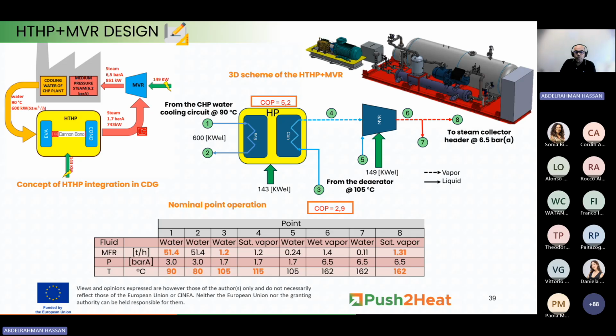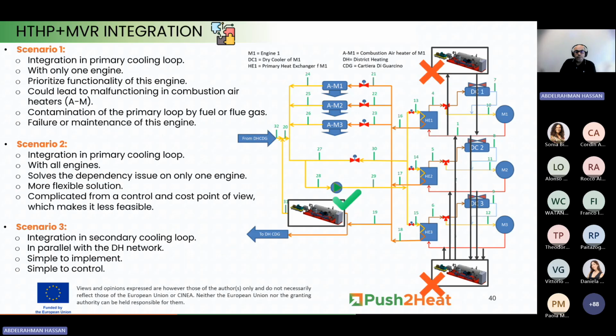Based on this nominal operating point and the data from the manufacturers, we have tried to figure out where we will integrate our system. The first scenario was integrating this system in the primary cycle with one of these motors. This solution was infeasible due to many challenges, like contamination of the primary loop, fuel or flue gases, or failure or maintenance of this engine. The second scenario was to integrate it with the 3 engines in parallel, and this is also a complicated solution, especially from the point of view of control and cost.